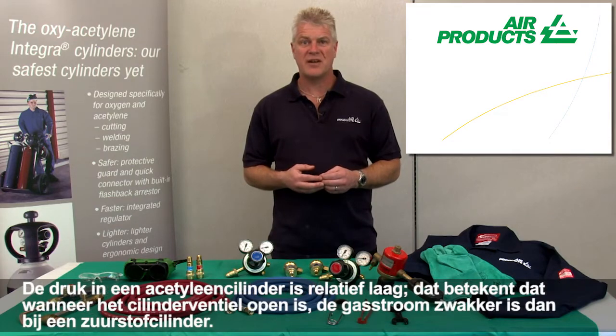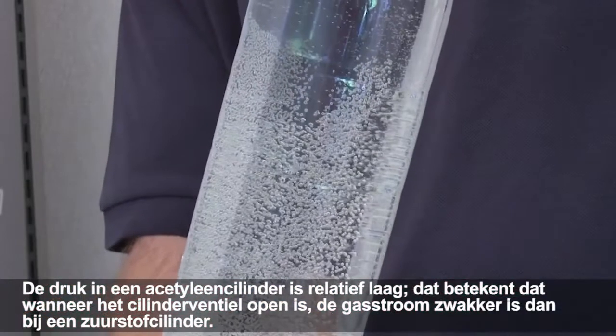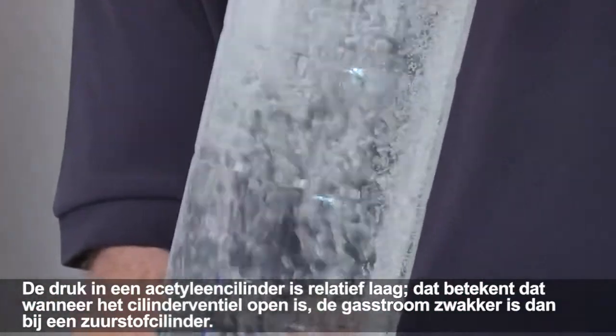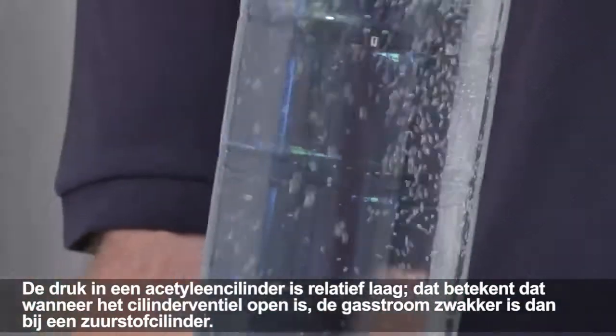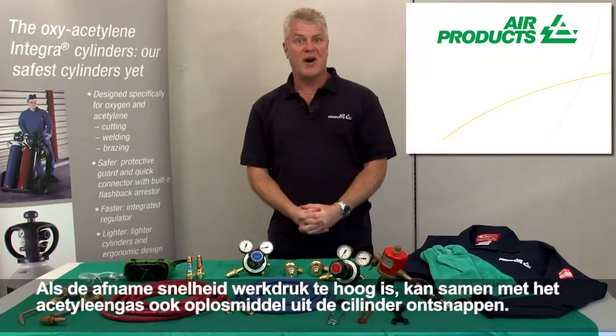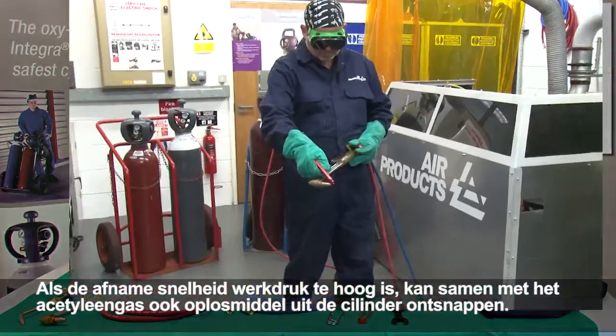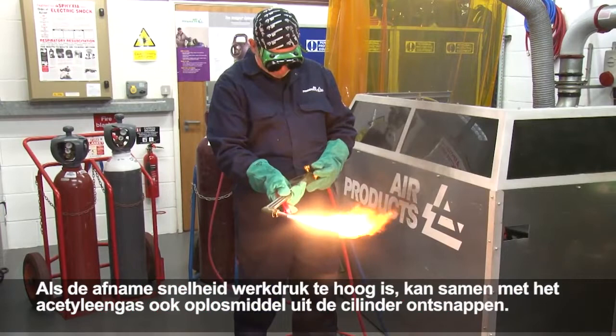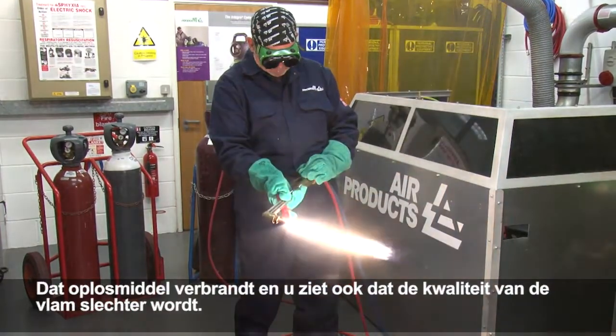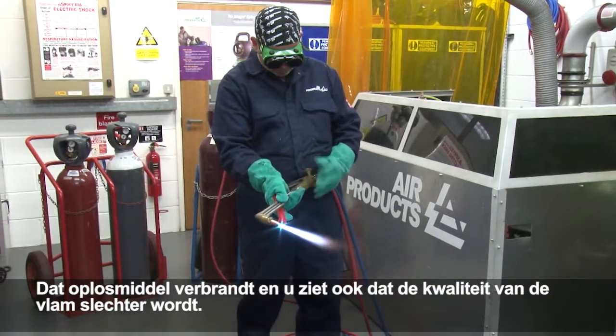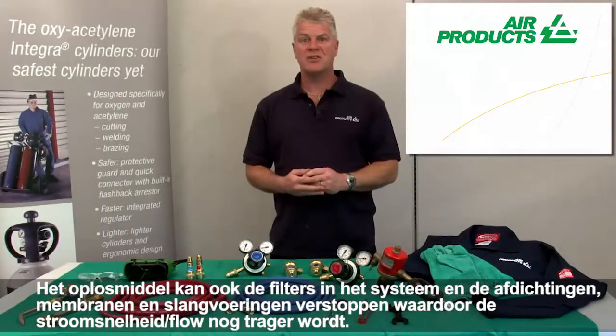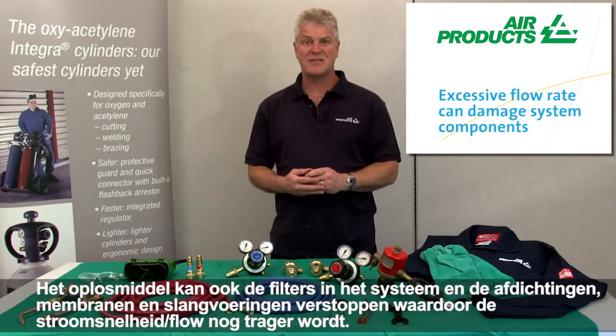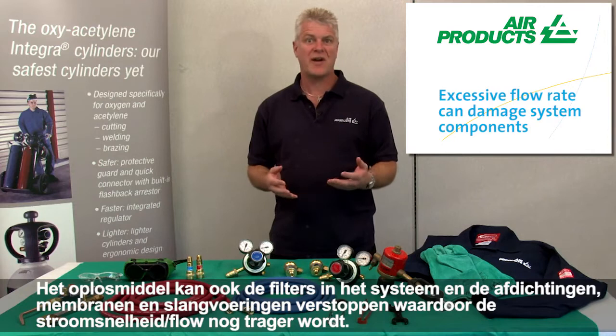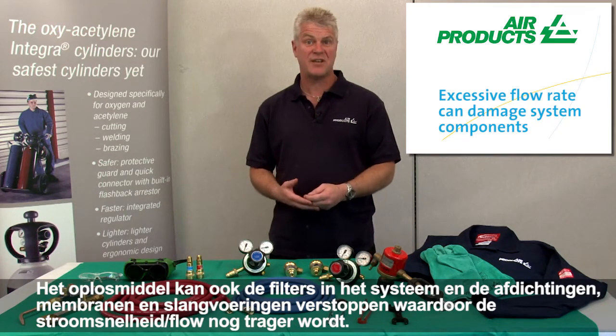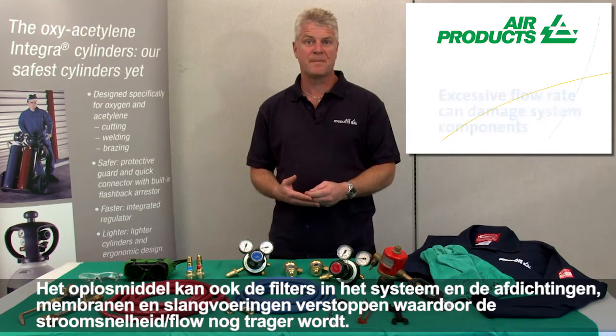The pressure in an acetylene cylinder is relatively low. This means that when the cylinder valve is opened, the gas flow is weaker than from an oxygen cylinder. When the withdrawal rate is too high, solvent can escape from the cylinder along with the acetylene gas. The solvent will burn and you'll see the flame quality deteriorate. It can also block the internal filters within the system, as well as damaging seals, diaphragms and hose linings, which can potentially further reduce the flow rate.